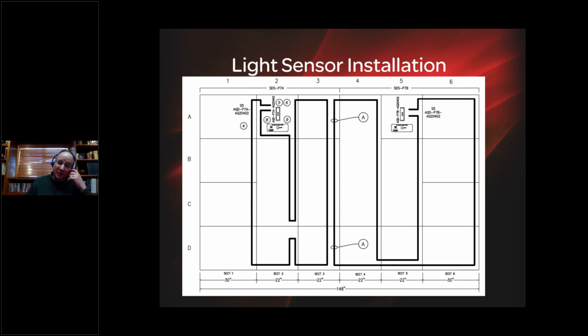By running the fiber in a motor control center, the way we run the fiber is to the left side of the buckets. We have a separate sensor in the wireway, but to protect the buckets, we have to remove all the buckets from the motor control center. There's typically a small space, only about a quarter inch, between the left side of the bucket and the left side wall of the MCC, and that's where we run these fiber optic cables. We can have up to 30 meter loops, approximately 90 feet per channel. Each of those sensor relays can support four channels, so we could have four 90 foot loops, which is plenty to cover even the largest motor control centers that I've personally encountered. Great question.